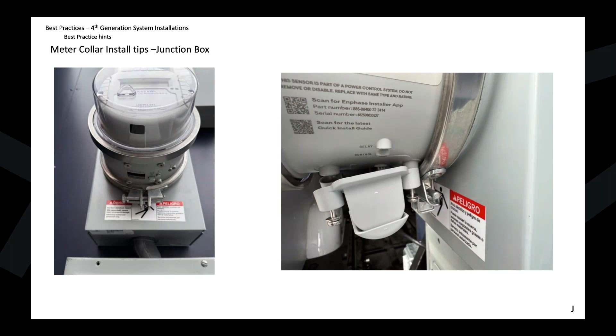Talk a little bit about the junction box on the meter collar. So make sure that you actually have those captive screws fully seated. As you can see here from an installation, they don't. They're leaving a clear gap from the junction box to the meter collar. Dust, dirt, water, snow, debris, insects, whatever. I mean, stuff can get in there. And what it does, it compromises the NEMA rating. So just be fully mindful of that.